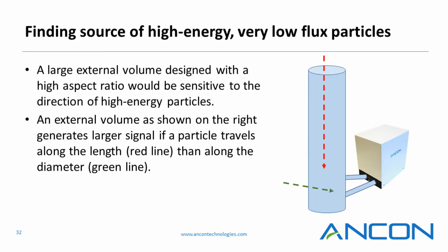An external volume, as shown on the right, generates a larger signal if a particle travels along the length, demonstrated by the red line, rather than along the diameter, shown with the green line.